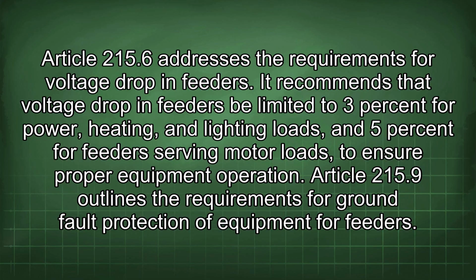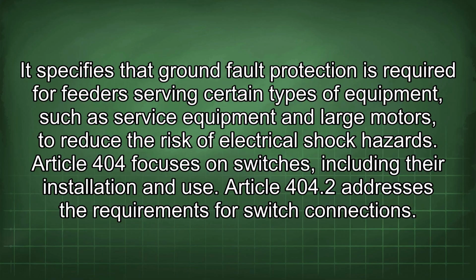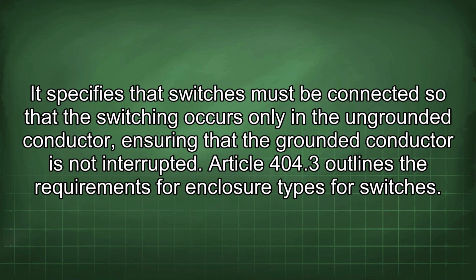Article 215.9 outlines the requirements for ground fault protection of equipment for feeders. It specifies that ground fault protection is required for feeders serving certain types of equipment, such as service equipment and large motors, to reduce the risk of electrical shock hazards. Article 404 focuses on switches, including their installation and use. Article 404.2 addresses the requirements for switch connections. It specifies that switches must be connected so that the switching occurs only in the ungrounded conductor, ensuring that the grounded conductor is not interrupted.